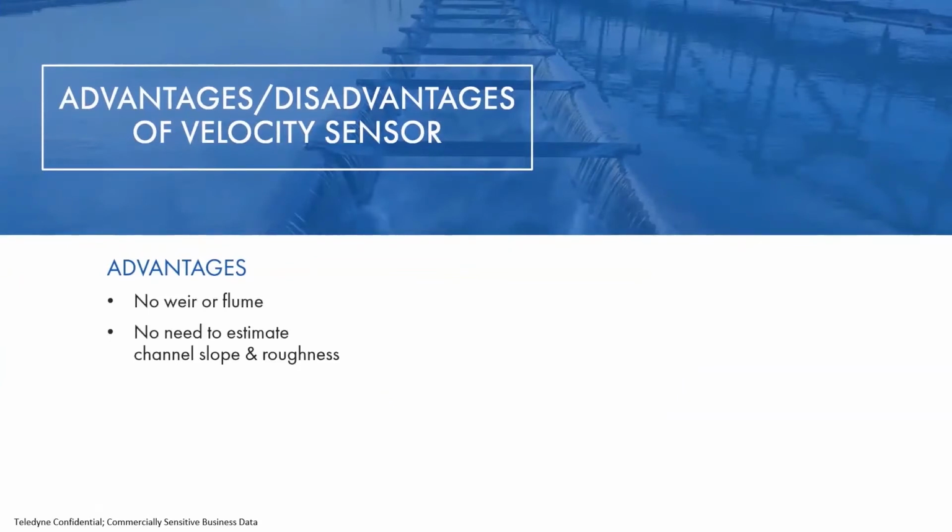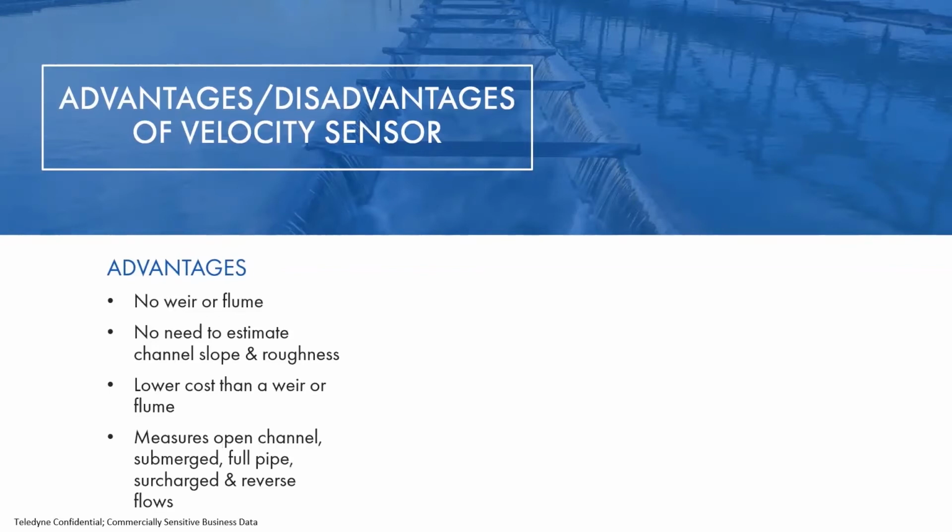So what are the advantages of an area velocity sensor? Well, no weir or flume is required. No need to estimate the slope or the roughness of your channel. And it's a lower cost than a weir or a flume, because you don't have to put in all the design work to put in a flume. Flumes can be quite expensive if you have to do a lot of excavating, concrete work, and there's a lot of things that could go into that.